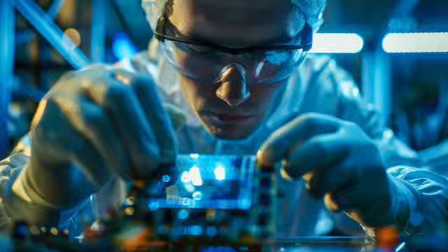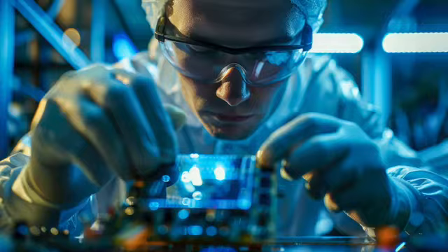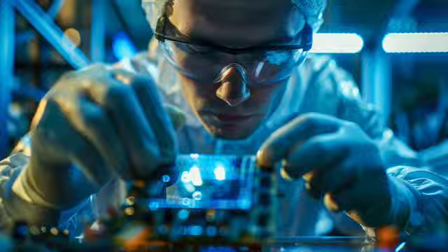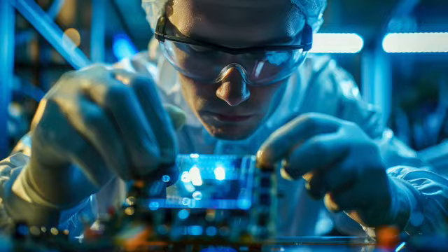And depending on the processes taking place, the air's humidity and temperature often need tight regulation. OK, what type of processes are we talking about that would need humidity control? Well, it could be whenever materials are sensitive to moisture loss or gain, they would need air humidity that was in balance with their moisture content. This then stops them drying out or absorbing moisture from the air. Or it could be a certain humidity level is needed to cause a reaction, like paint or glue curing, or even stop a reaction.